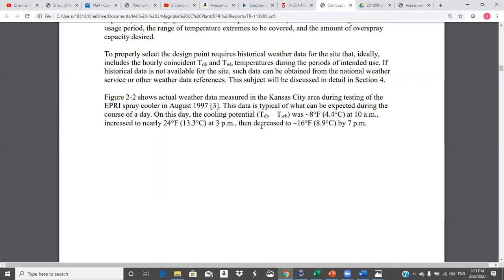This is called what? Approach to, there's another term they use. But see, the wet bulb is the limit. If you can saturate the air completely going through the evaporative device, you can get to the wet bulb temperature. You can't get below the wet bulb because when you get to the wet bulb, you're saturated, you can't evaporate anymore, okay? So the dry bulb outside minus the wet bulb outside is the potential wet bulb depression. So how much can you depress the dry bulb by evaporating to the wet bulb? So that's what this is.